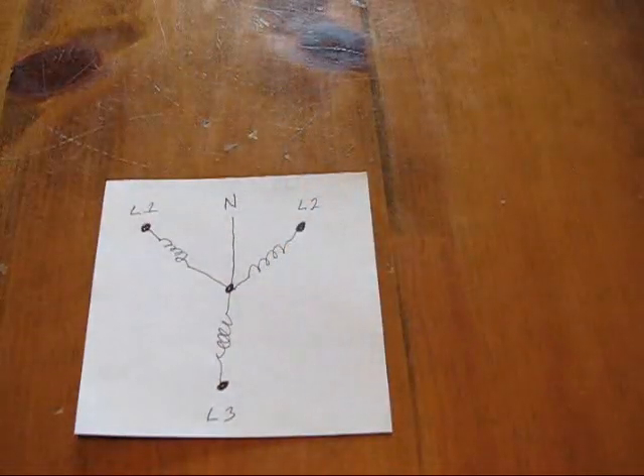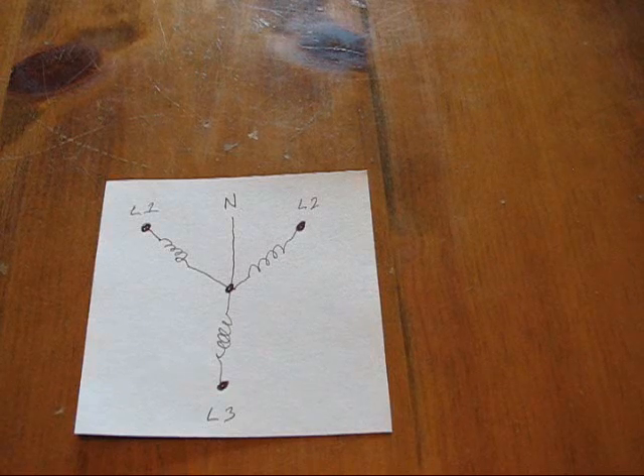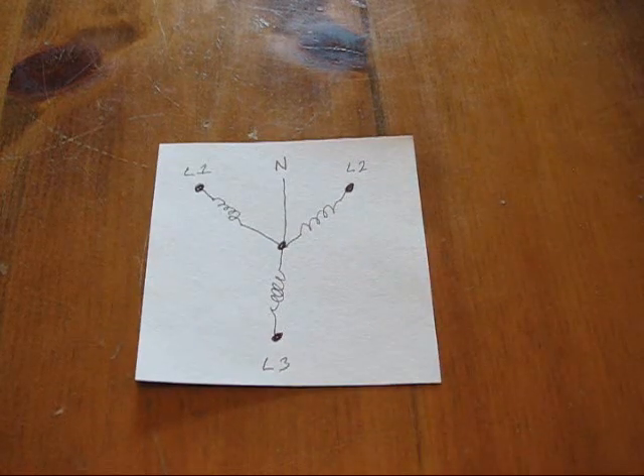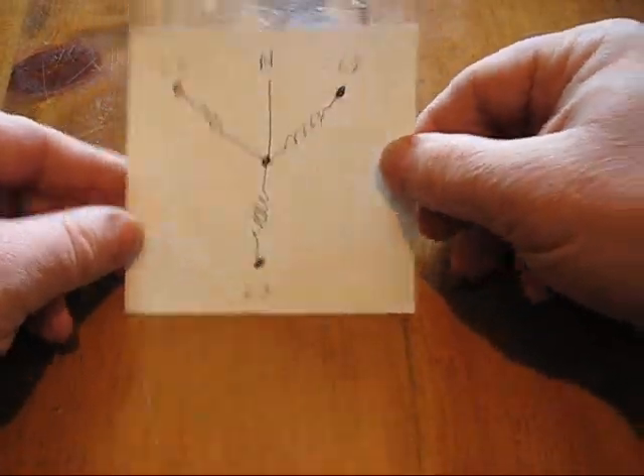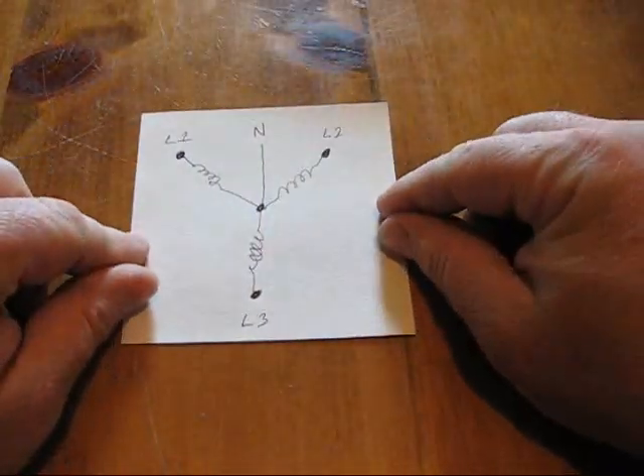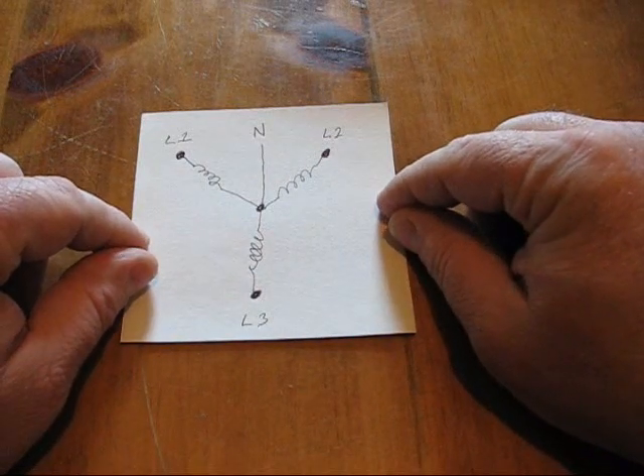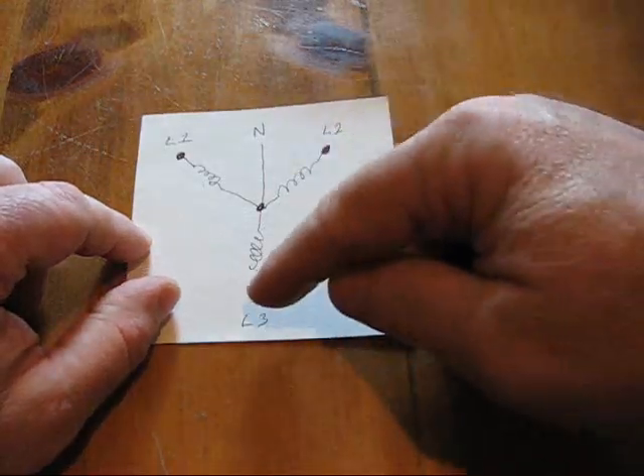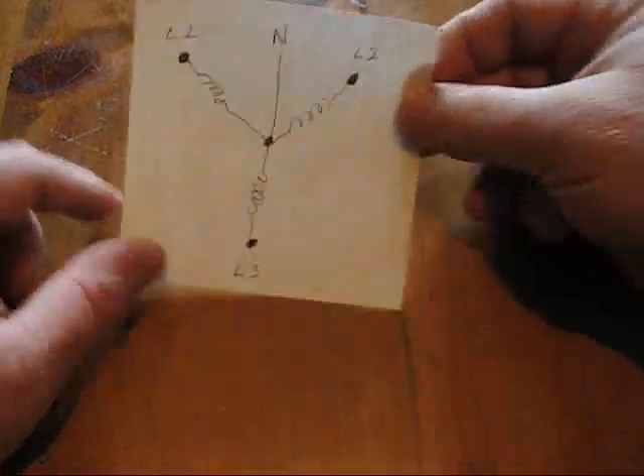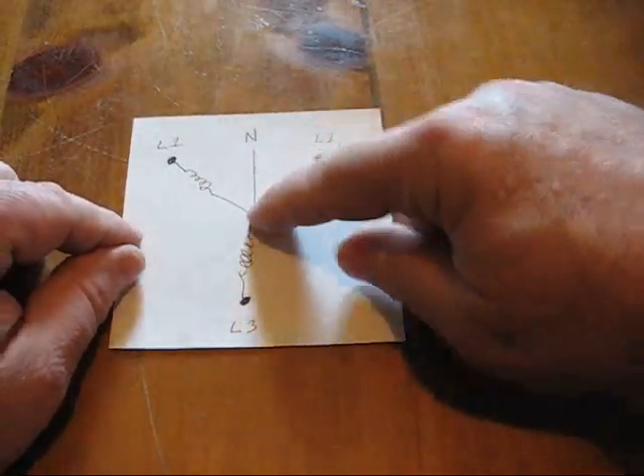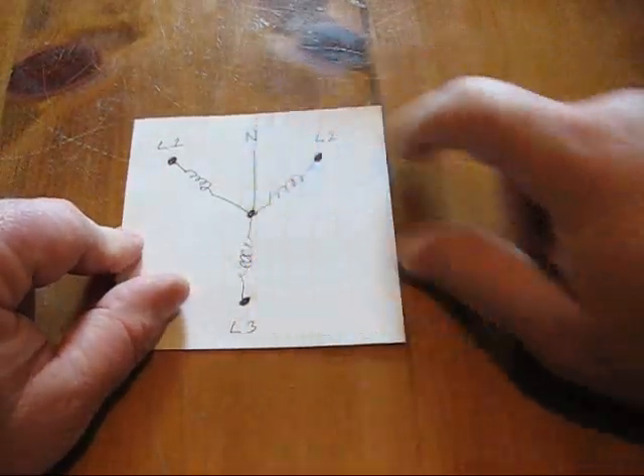This is what it looks like. That's called a Y connection, also called a star connection. That's the three coils of the stator in a generator. You have line one, line two, and line three, which are all the hot legs. And in the center where the three are connected, you have neutral.